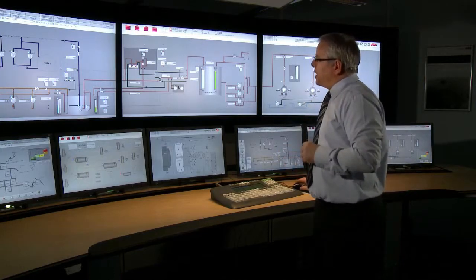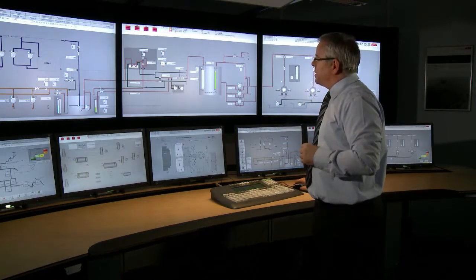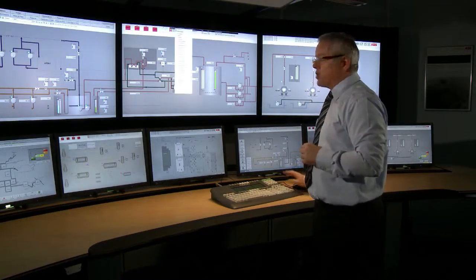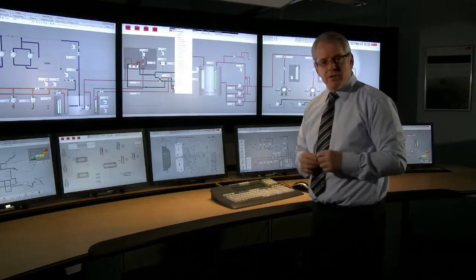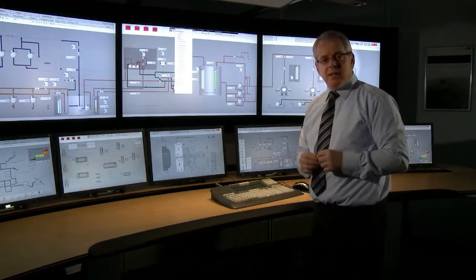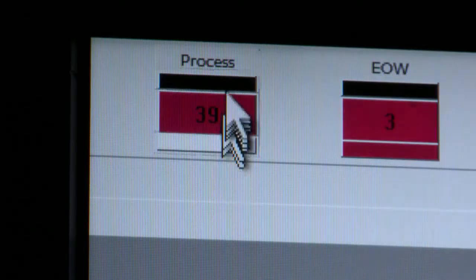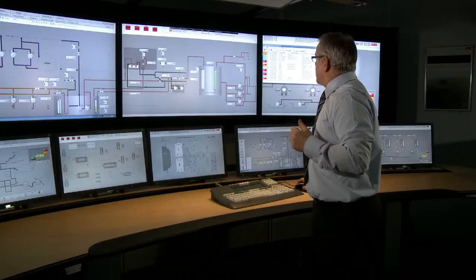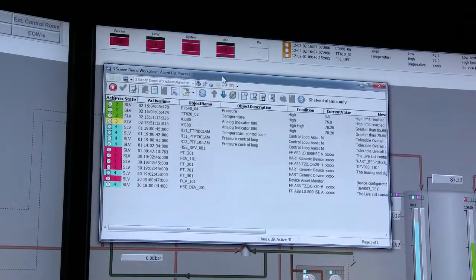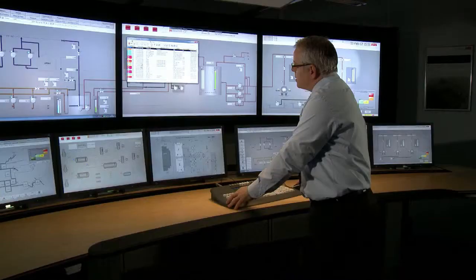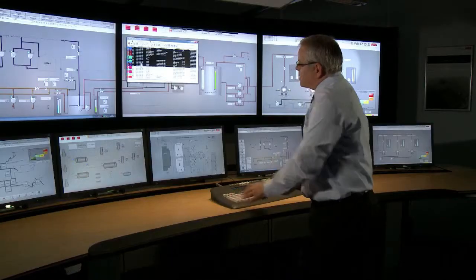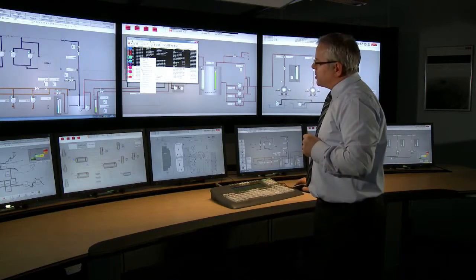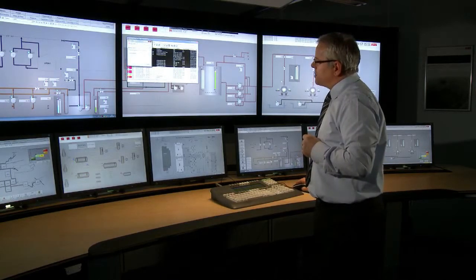Some of the functions available inside of 800XA are the alarm shelving and the alarm hiding functions depicted within the 191 guideline. If I want to simply shelve an alarm, I bring up the alarm list here and either select an individual alarm or a group of alarms, and by a simple right-click I'm able to shelve those selected alarms.